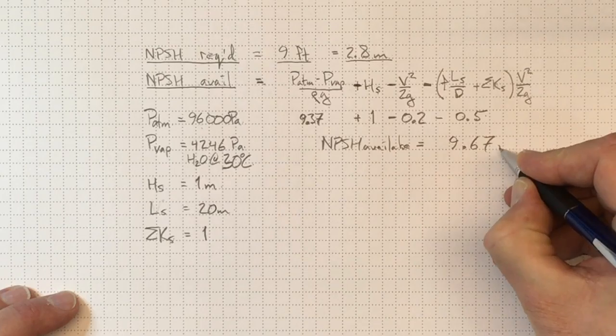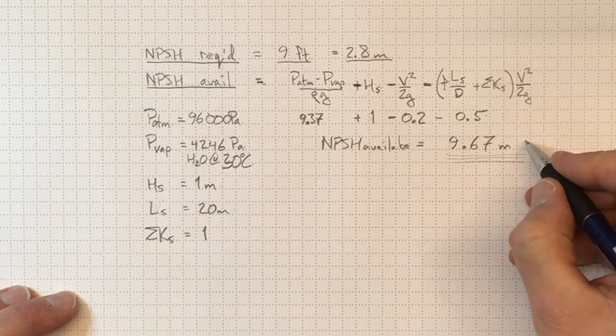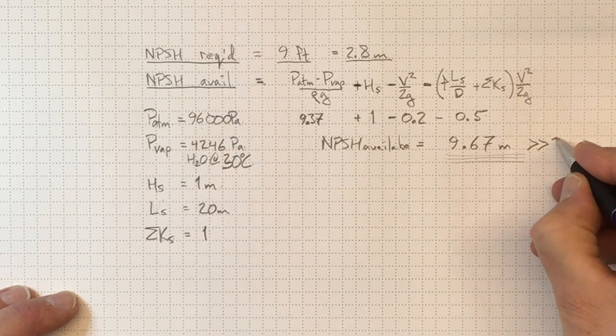So with 9.67 meters of NPSH available, we're much, much greater, well, significantly greater than the 2.8 meters that we require.